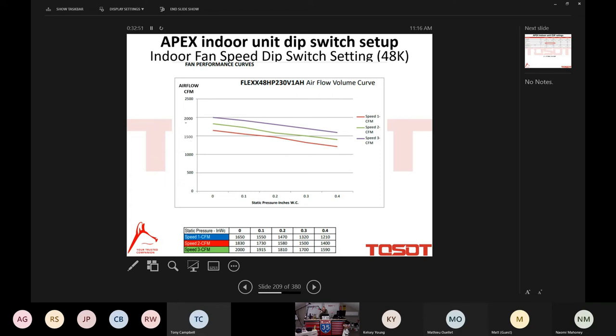But my point being here is this is from the submittal sheet. The submittal sheet will answer, I'm going to say, 80% of your questions in a single sheet, double-sided piece of literature. So I always strongly suggest when you have a question, a specification issue, go to the submittal sheet for that product. That's what you're looking at here. You can see what CFM the three different speeds on that unit will produce.